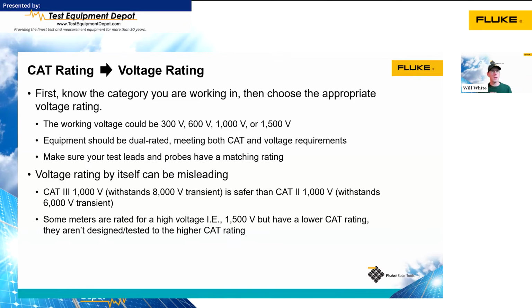Another interesting point, and this I've found with meters that are coming from being imported specifically from China, although some European models as well, they may claim to be able to test up to a certain voltage, but when you look at the category and voltage that they're actually rated to, they're lower than that test voltage. So they may say that the meter can test up to 1500 volts or even 2000 volts, but when you look at the category rating, it might be only category 3 1000 volts. So that's something to look out for, because they don't have the safety factor built in that a tool that was appropriately rated would have.